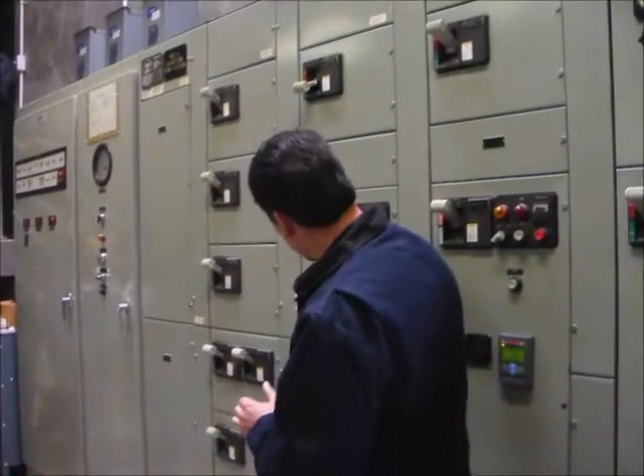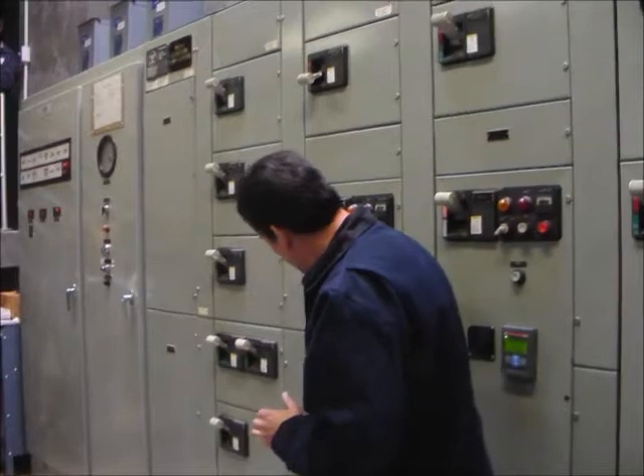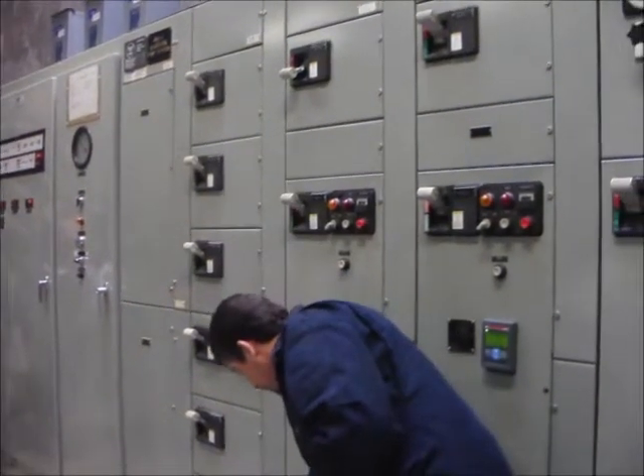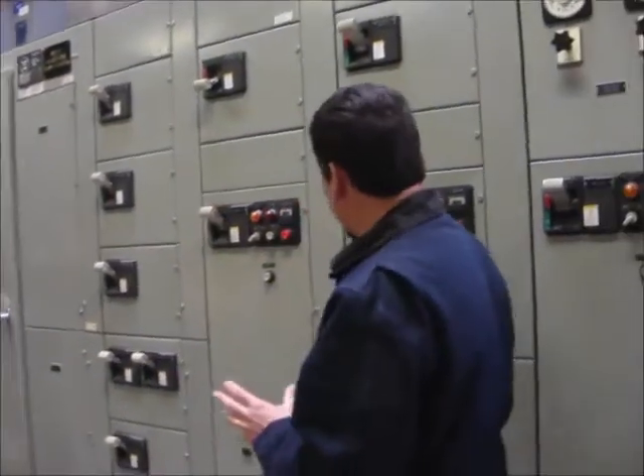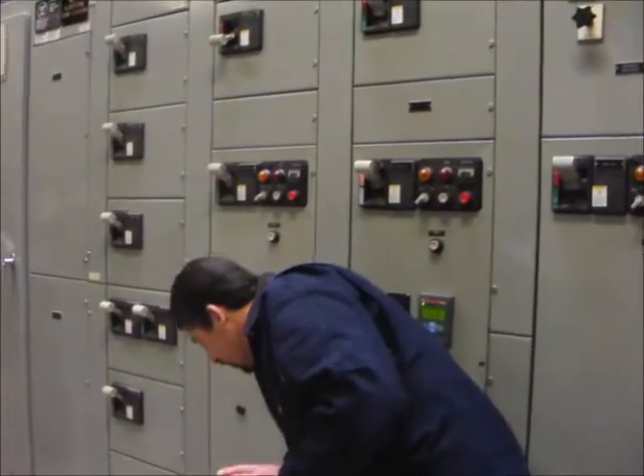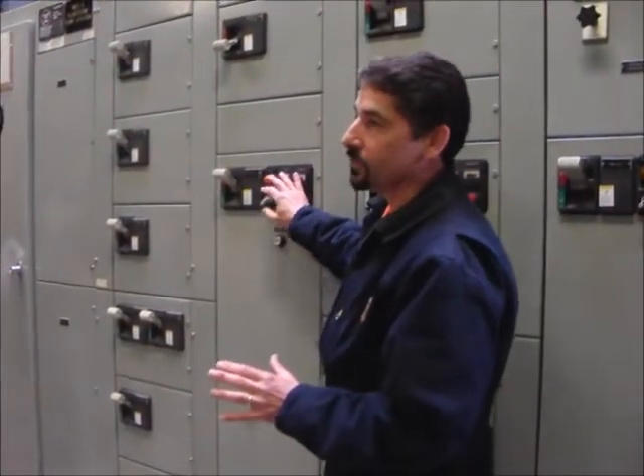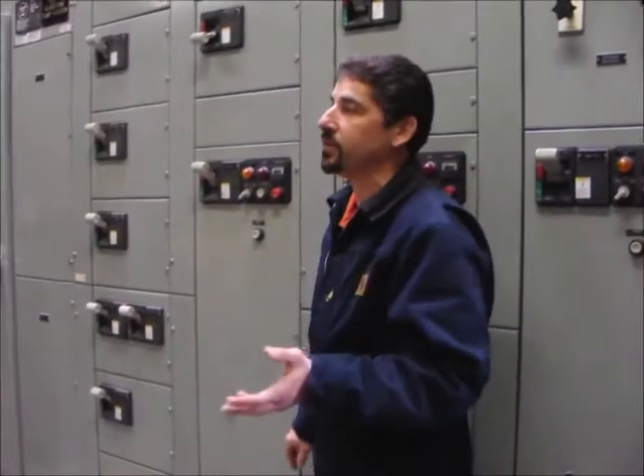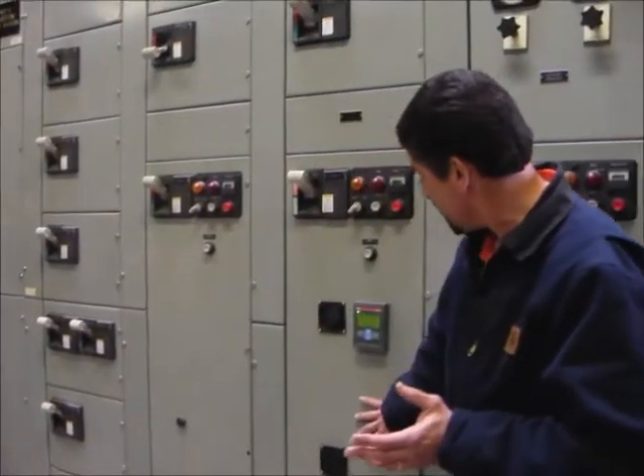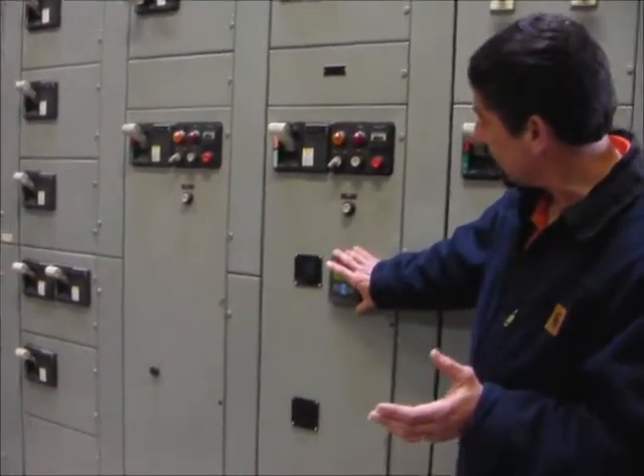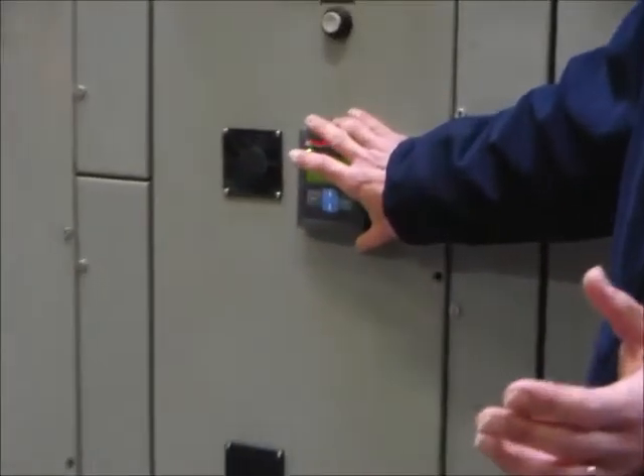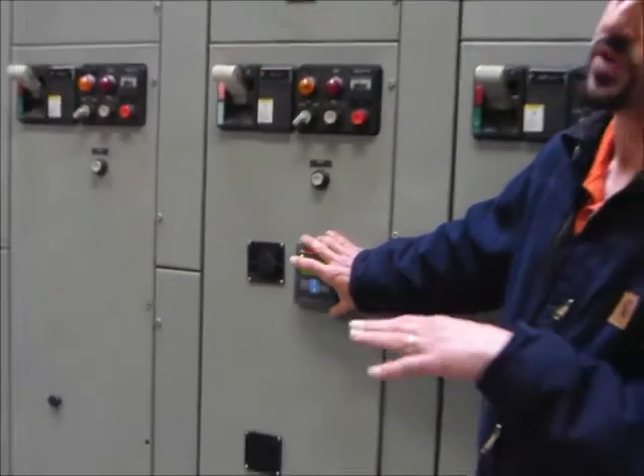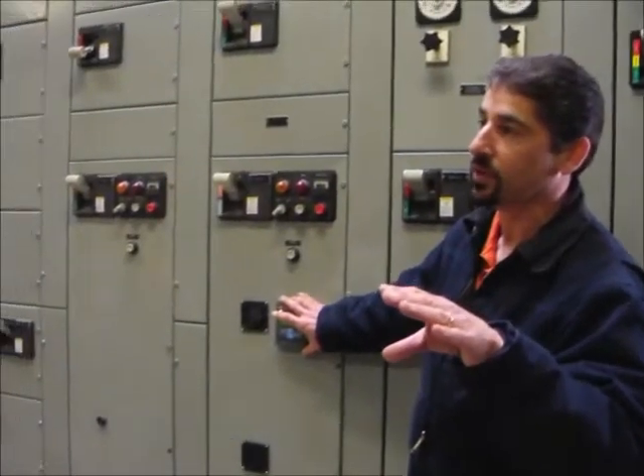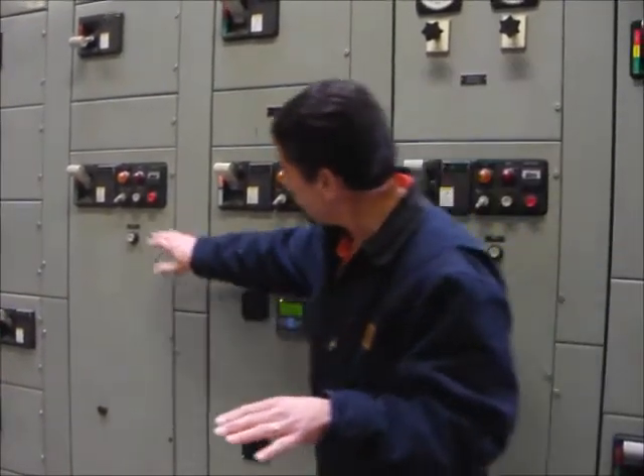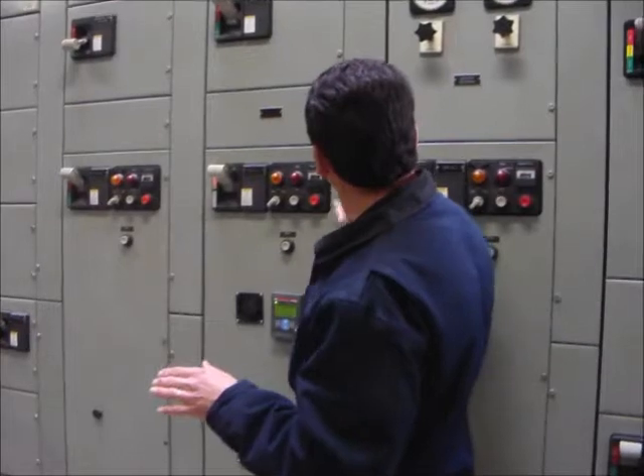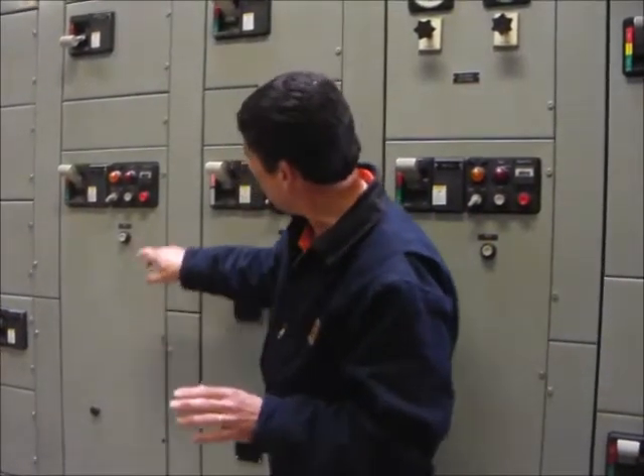That's the old system. There's 3 big transformers and 3 big switches in here, switch gear and a big transformer on the bottom. What happened a while back is the transformer caught fire and burned out the whole bucket. So we decided to update it to the newer stuff, which was this. Basically, it's a VFD soft start, but it's not a VFD. I can ramp this soft start to do different things, how I want it to start. So you got this big panel. If I can open it up, I'll show you. I'm not going to do that.